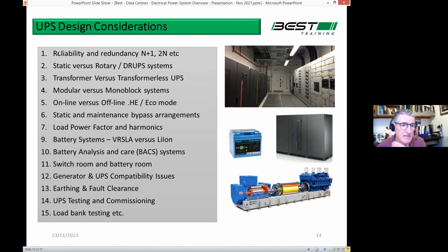So in terms of UPS, what do you look at? Reliability and redundancy is important in all aspects of a data center, but it really comes to the fore when you're looking at the UPS system, whether you go for N+1 or 2N level of redundancy. Static systems versus rotary. The system in the top diagram is a static system. It's electronic components which convert the power back to AC, and there's the batteries, which aren't shown in the diagram because they're stored in a separate room. The battery system is your short-term storage.